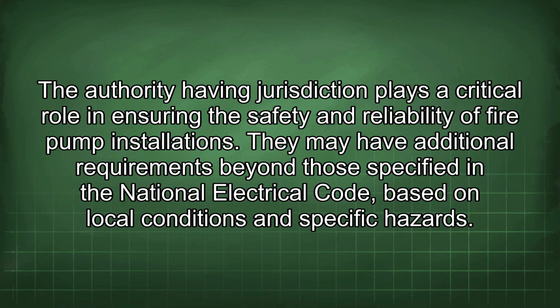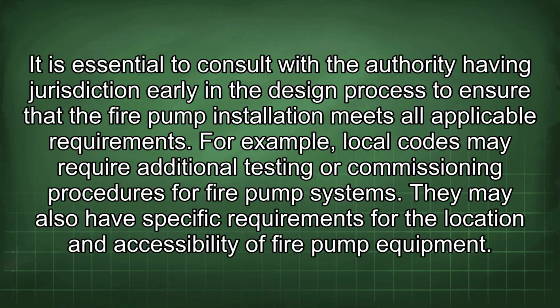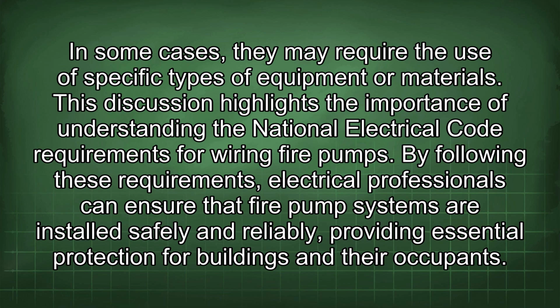The authority having jurisdiction plays a critical role in ensuring the safety and reliability of fire pump installations. They may have additional requirements beyond those specified in the National Electrical Code based on local conditions and specific hazards. It is essential to consult with the authority having jurisdiction early in the design process to ensure that the fire pump installation meets all applicable requirements. For example, local codes may require additional testing or commissioning procedures for fire pump systems. They may also have specific requirements for the location and accessibility of fire pump equipment. In some cases, they may require the use of specific types of equipment or materials.